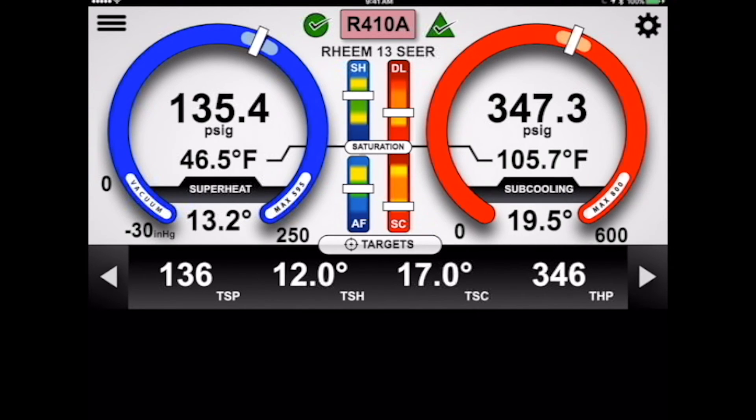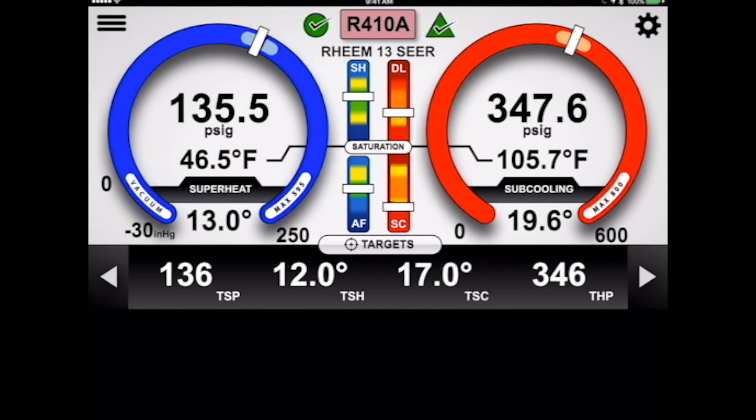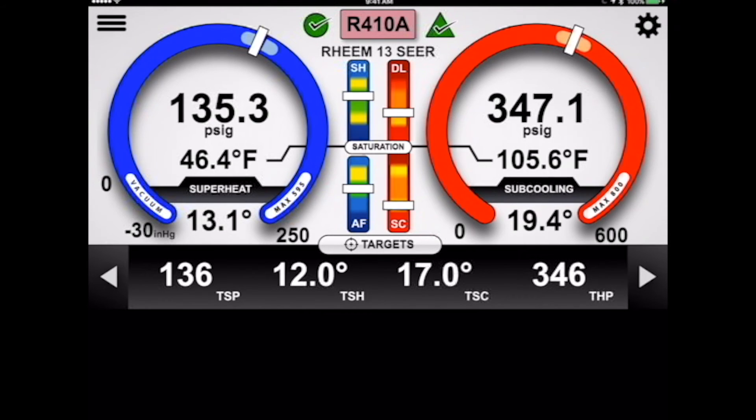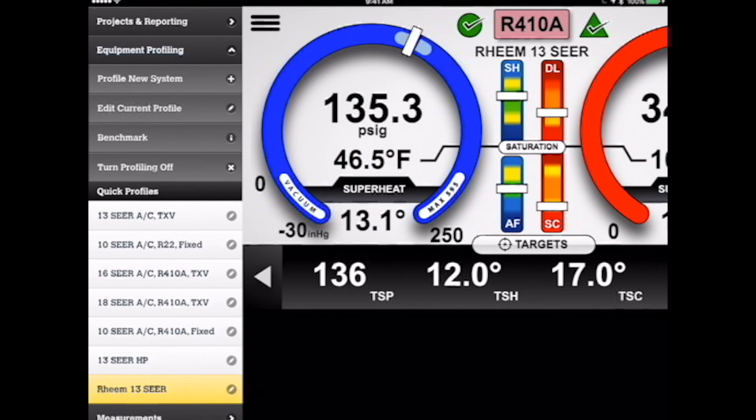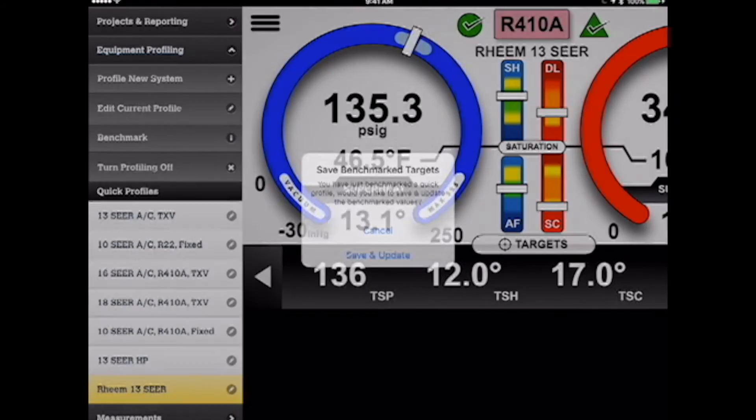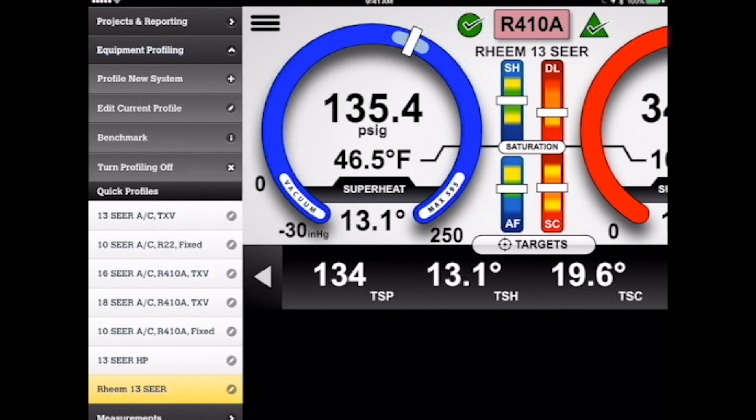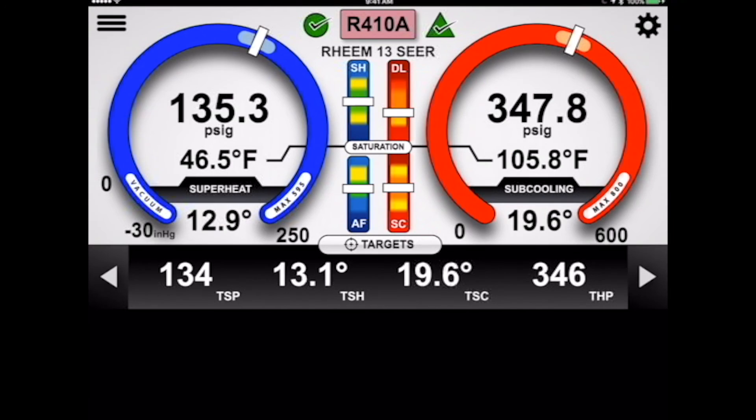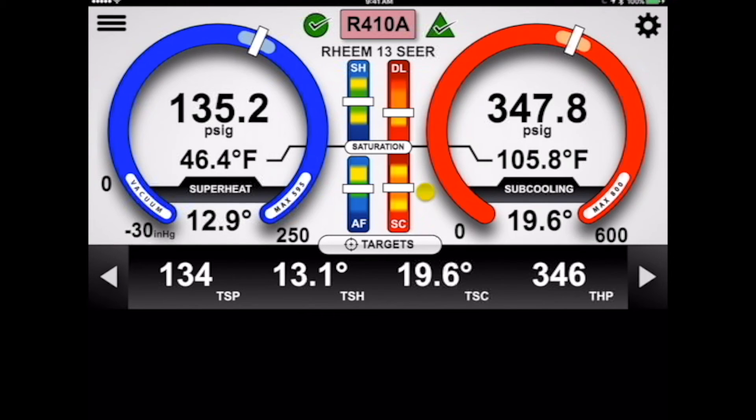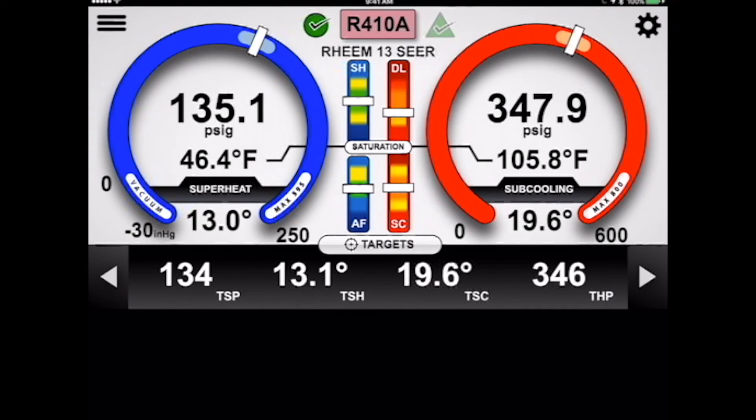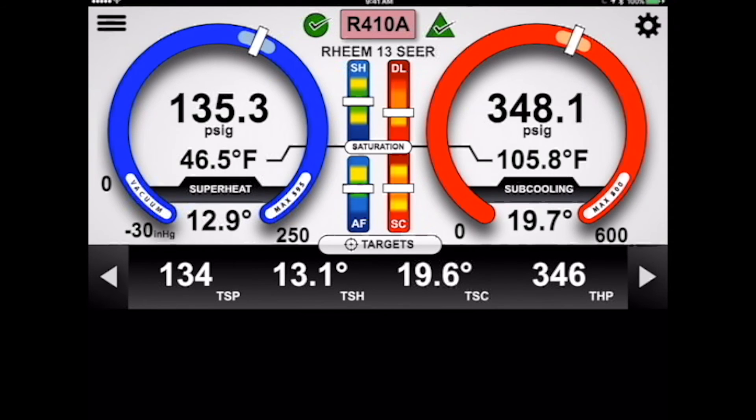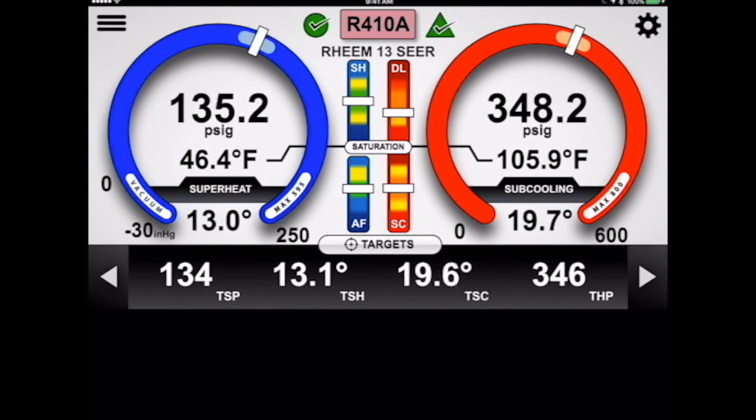So, again, this allows us to see not only what the readings are, but now are they where they should be? So we're going to go ahead and I'll show you the next real powerful feature of this, and that is being able to store this in the cloud as a benchmark. So we go in there, and if we benchmark this system, what we're going to do is I'm recording exactly the way that system's operating. You can see right here that that subcooling went right to the center. The subcooling went right to the center, superheat's at the center.